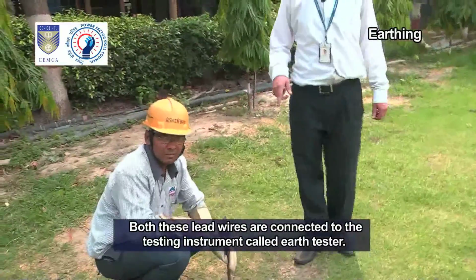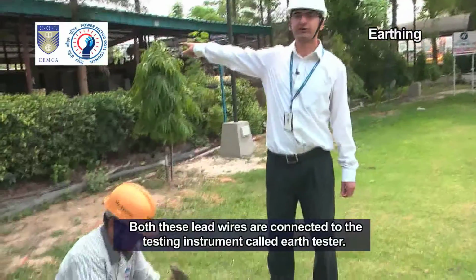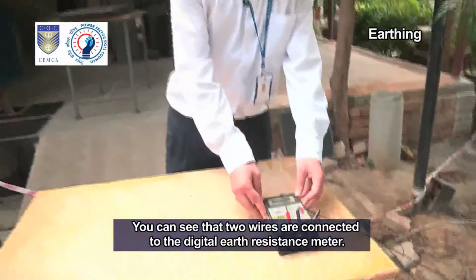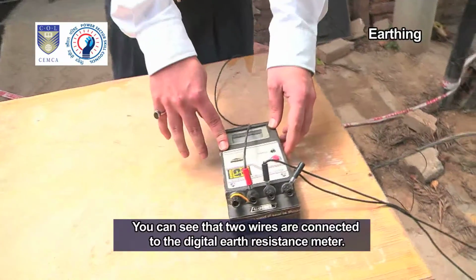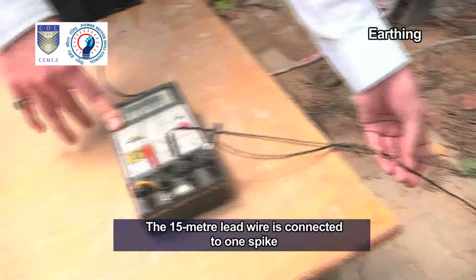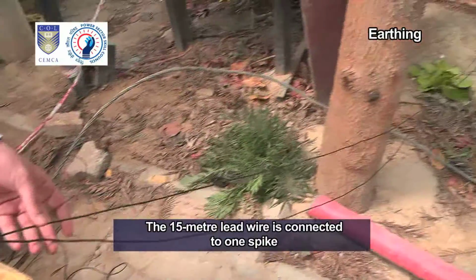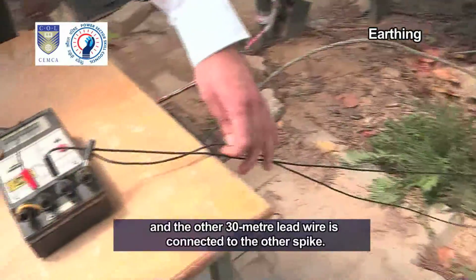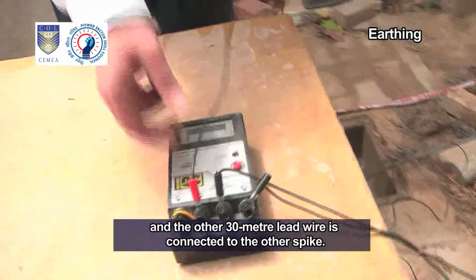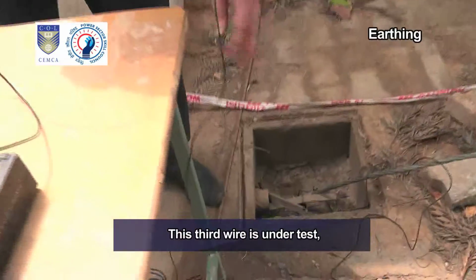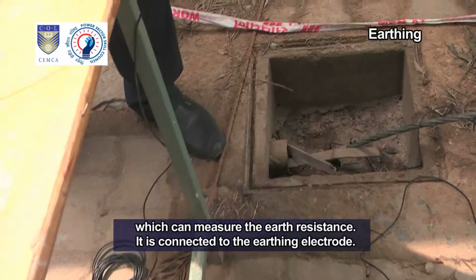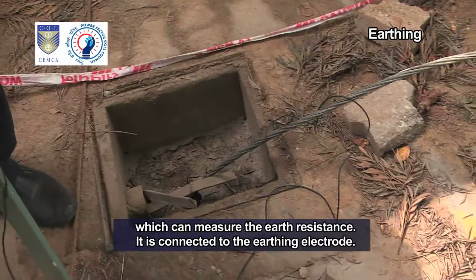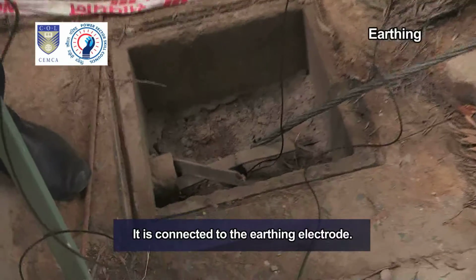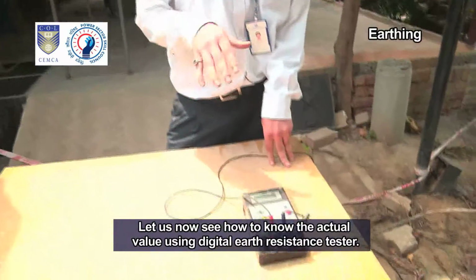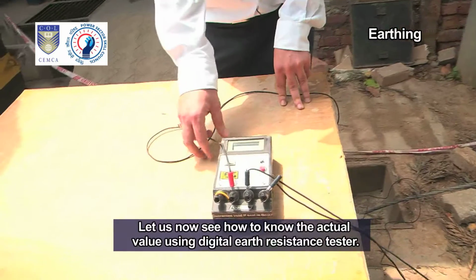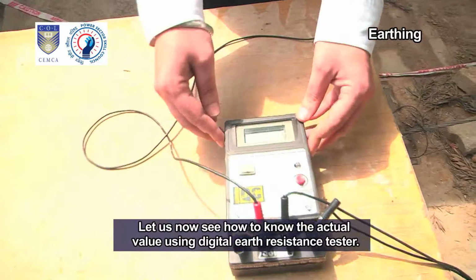Both these lead wires are connected to the testing instrument called earth tester. You can see that two wires are connected to the digital earth resistance meter. The 15-meter lead wire is connected to one spike and the other 30-meter lead wire is connected to the other spike. This third wire is under test, which can measure the earth resistance. It is connected to the earthing electrode.